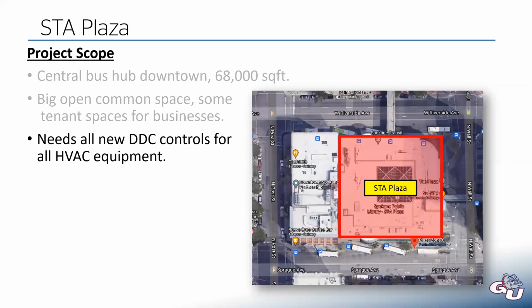So as a reminder, DDC, that's the high end of the controls offerings that we talked about. So that is where they get a centralized front end where they can look at all of their equipment on a computer screen. They can look at the status of equipment, see what temperatures are being read. They can change schedules and set points and all of that good stuff. They had an existing DDC system, but it was about 20 years old. And in the DDC world, that is essentially ancient technology.